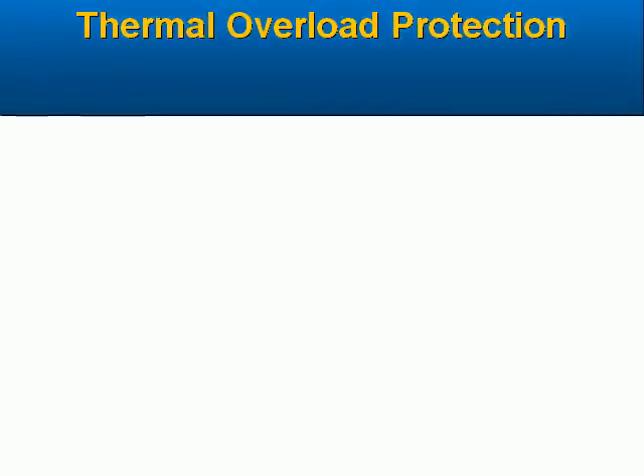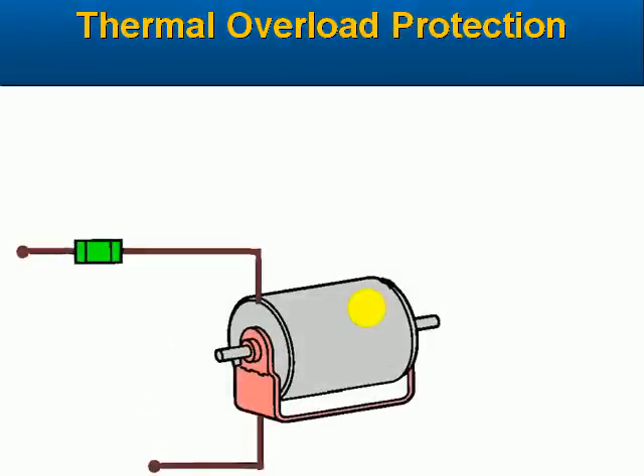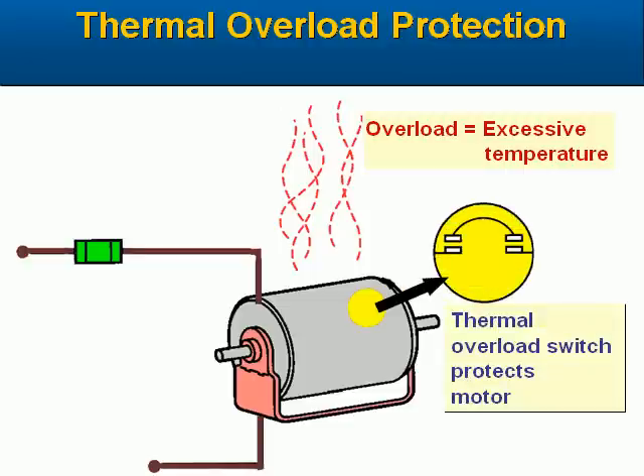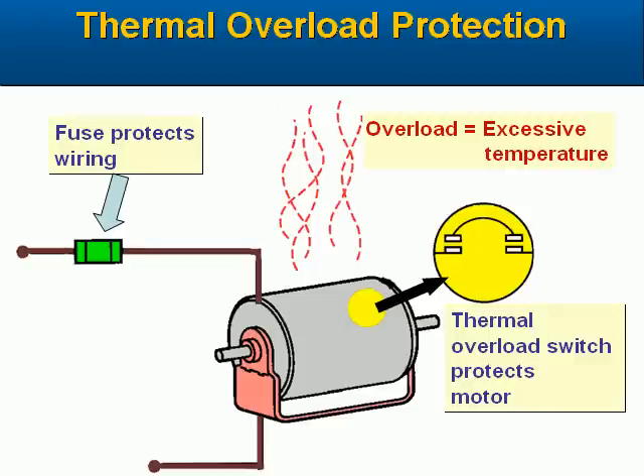In some instances, additional protection may be needed. Electric motors under stress may overheat, damaging the insulation on the windings inside them. The circuit breaker or fuse protecting the circuit may not receive enough current to trip. Thermal circuit breakers can be employed inside the motor to protect it from excess heat that results from excess loading. Such circuit breakers can be manually or automatically reset once the motor cools off.